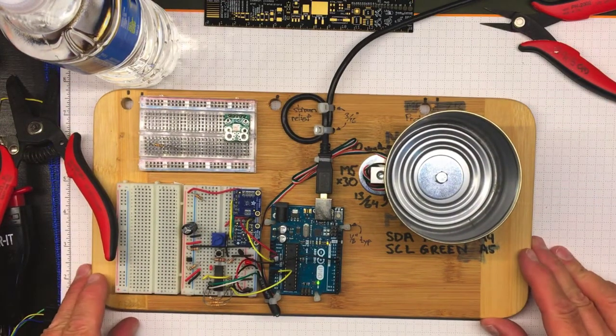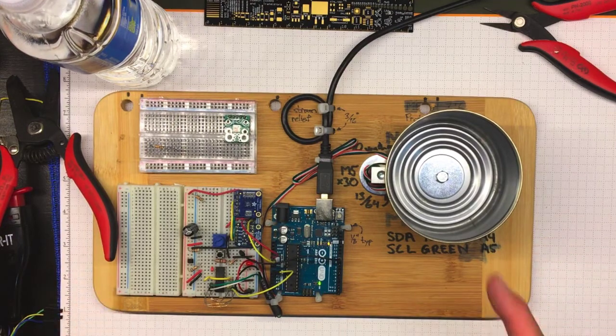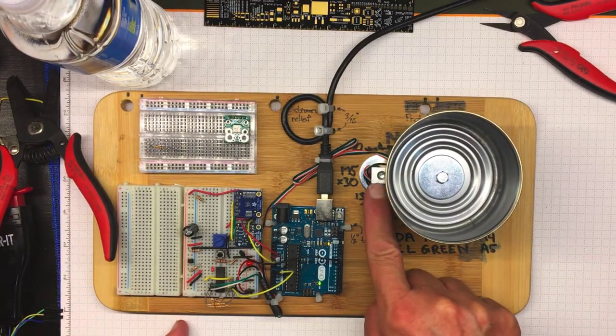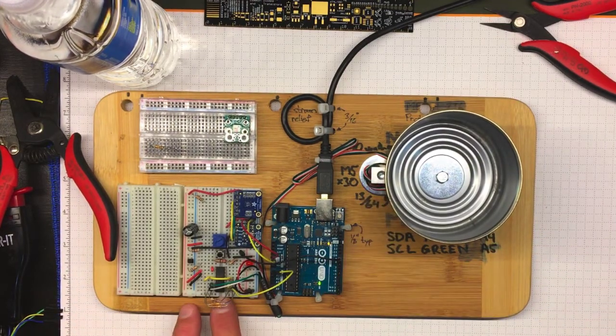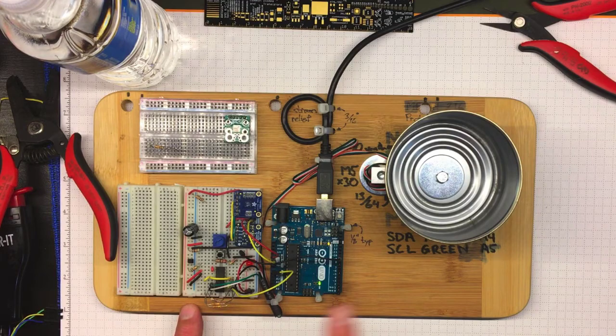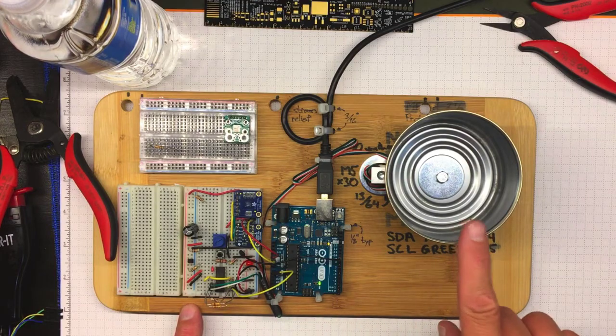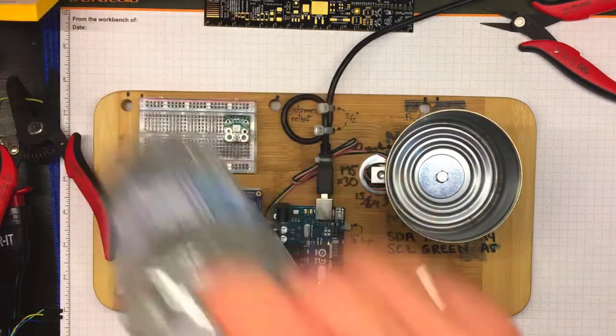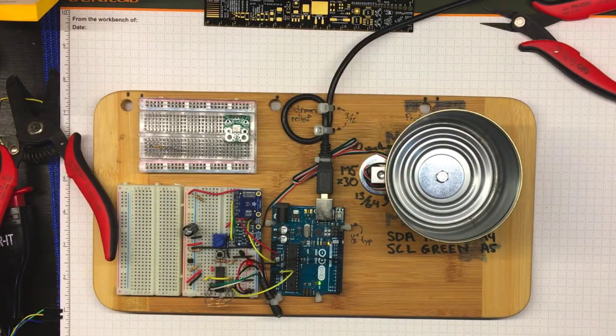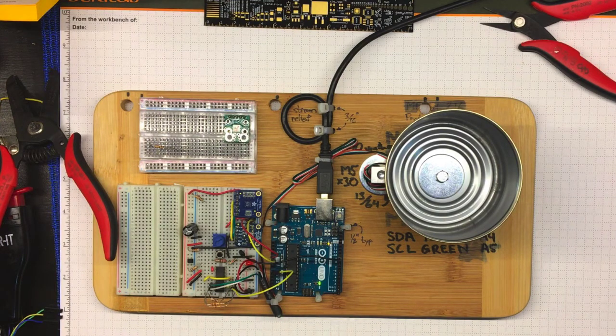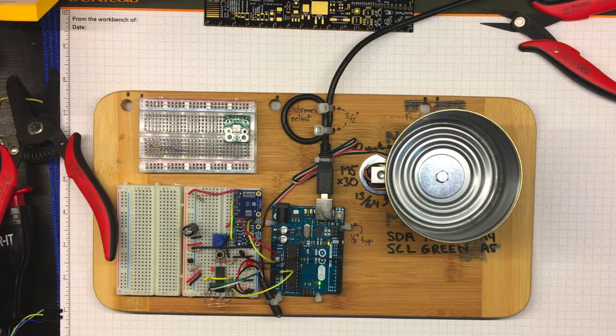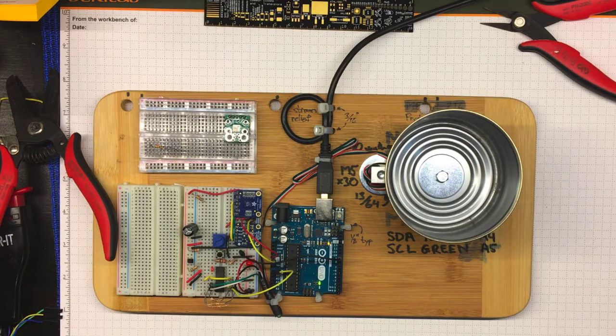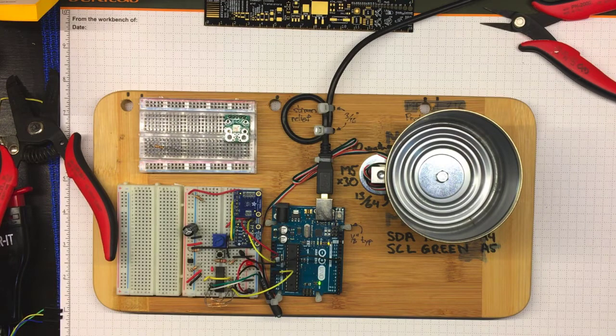Now if I take this setup, I know the sensitivity here, I know the gain that I've applied. I should be able to figure out the applied mass just by calculating through all the numbers without doing any calibration. It won't be as accurate if I do it that way, but it will at least get me started.